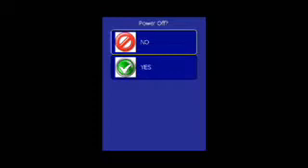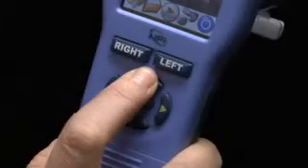The pupillometer will turn itself off after 60 minutes of inactivity outside of the charging station. However, to turn the device off immediately, navigate to the power icon on the main menu. Then, press Yes to confirm that you would like to shut the device off. To turn the pupillometer back on, either place it in the charging station or hold the up arrow down for 3 seconds.